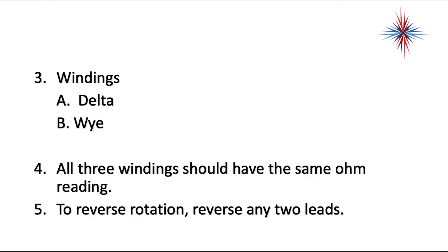There's two winding configurations, a delta and a Y configuration. All three windings should have the same ohm reading. That's extremely important when you're troubleshooting. That's a big difference from single-phase equipment. Single-phase equipment, you'll remember start, run, and common all have different ohm readings. In three-phase, that is not the case. You do not have a start, run, and common. You have an L1, L2, L3.